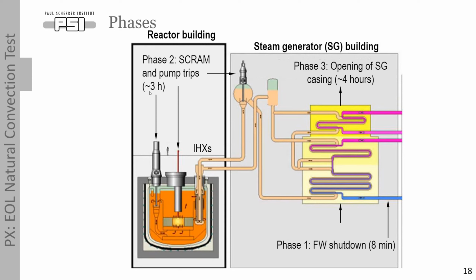After these 3 hours, the next step was opening of the steam generator casing. I already showed you the steam generator, and I told you that there were windows or doors. And these windows, after these 3 hours and 8 minutes, were opened. This allows atmospheric air to enter the casing and remove decay heat. And this last phase lasted 4 hours.